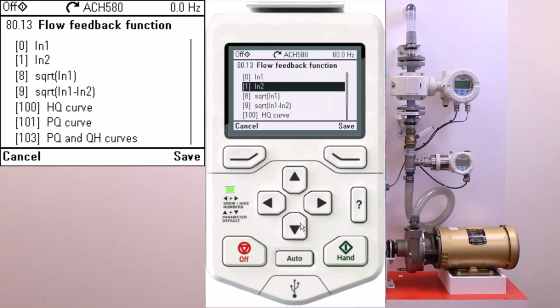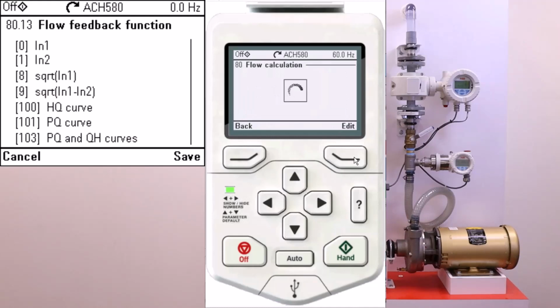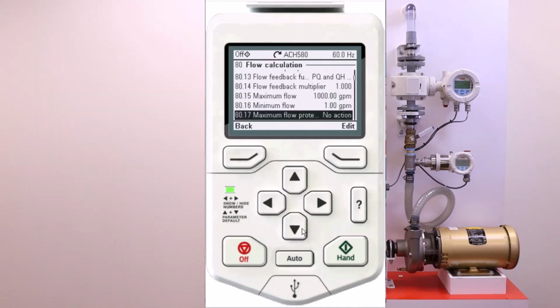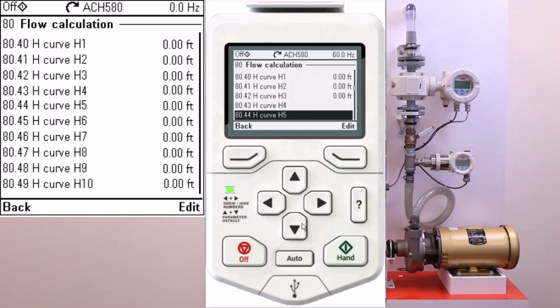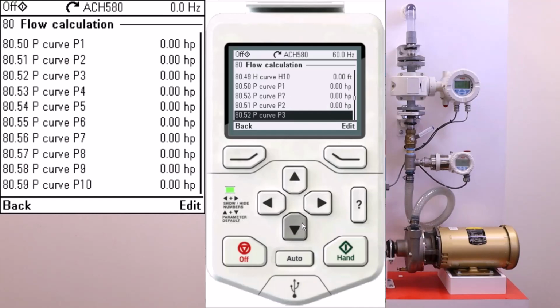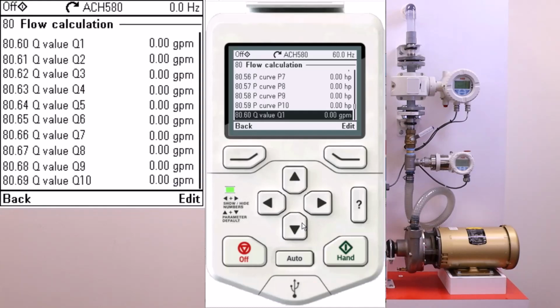And if you look down, you see we have option 100 here is HQ curves. That's head to flow curve. And there's PQ curve, that's power to flow curve. And then there's power to flow and flow to head curves. That's our sensorless pumping section. So I save that. Once that happened, a whole new set of parameters have now opened up in Group 80. And if I go down here, here's our curves. H1 curve through H10. Then we got P1 in horsepower through P10. And they say horsepower because I converted that to horsepower earlier. Then Q1 all the way up to Q10 in gallons per minute. And that's because we went into Group 81 and put gallons per minute in.